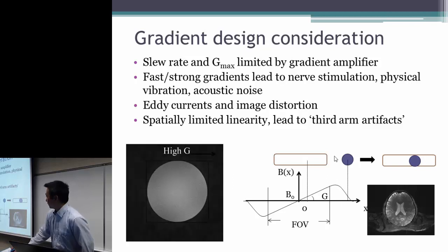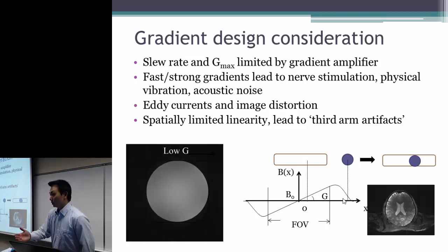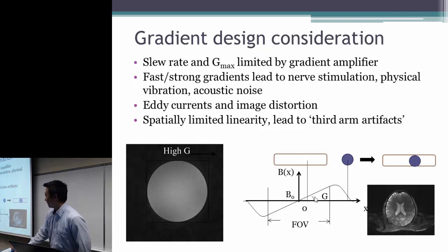And if you are using an RF pulse, that also excites all the signals here. So that means in the reconstructed image, the objects outside the field of view will also be considered to have the same location as the original object, so that they will overlap.